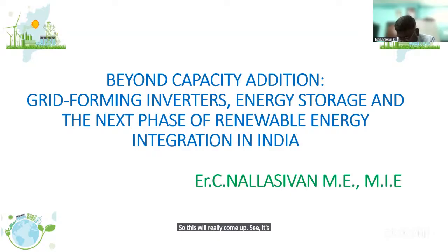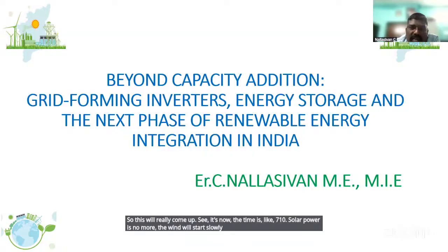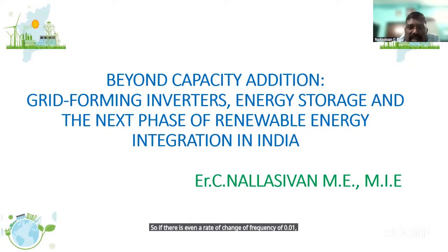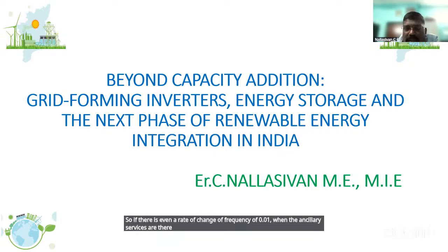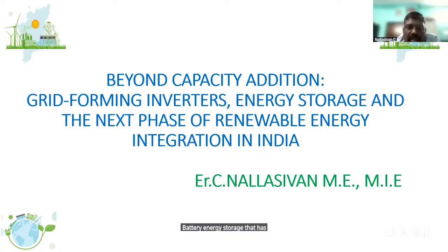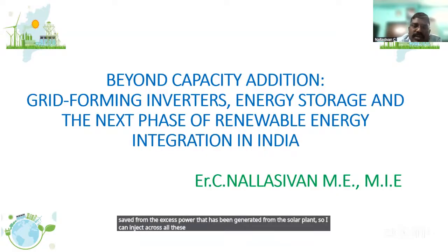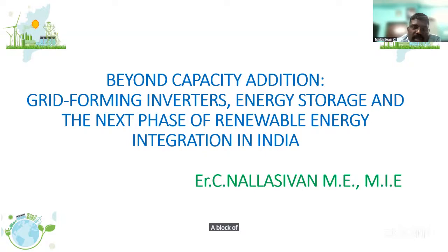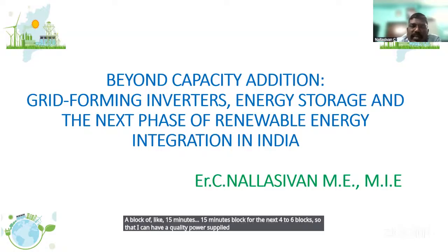See, it's now 7:10. Solar power is no more, the wind will start slowly. So if there is even a rate of change of frequency of 0.01, when the ancillary services are there, the grid planners from the load dispatch centers know that at this time I have, say, 1,000 megawatt-hours of battery energy storage saved from the excess power generated by the solar plant. So I can inject across all these buckets for the next cycle, in 30 minute or 15 minute intervals, for at least a block of 15 minutes for the next 4 to 6 blocks, so that I can supply quality power during the evening peak periods across various important junctions, wherever I have my weak nodes.